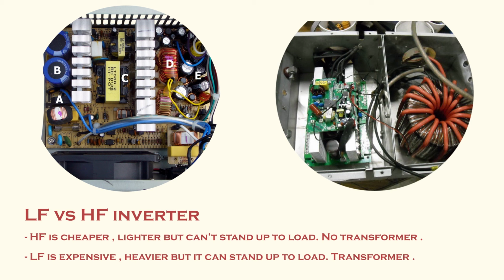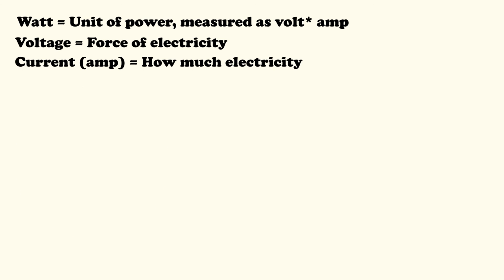I actually got a 25,000 watt continuous load inverter that can handle surges up to some ridiculous number, far more than I need. The only reason I got that big an inverter was to handle higher loads and not worry about things burning out. I didn't want to shortchange the inverter, so I spent a little extra to get a low frequency inverter big enough to handle my entire load.